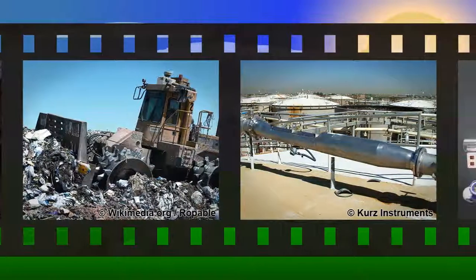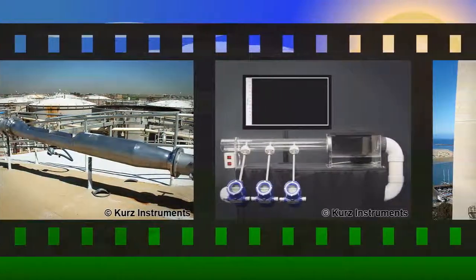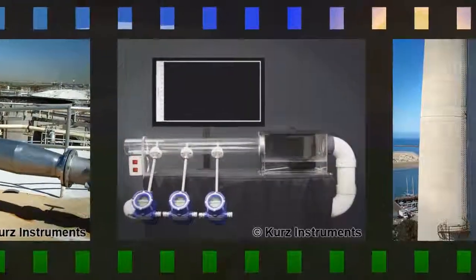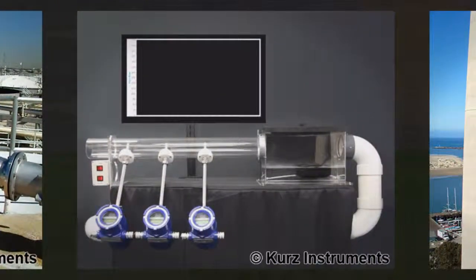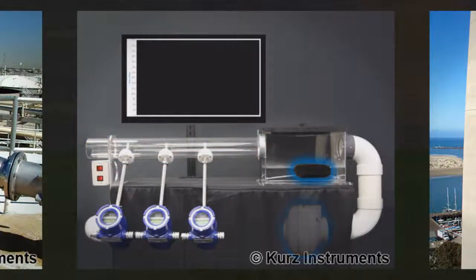The Kurz wet gas simulator is a fog generator that reproduces the moisture-laden environment found in digesters, landfills, and wet stacks. The simulator is designed with a flow loop using a 3.5 inch pipe, a fan, and a mist generation unit with the surrounding air brought to 80% humidity.